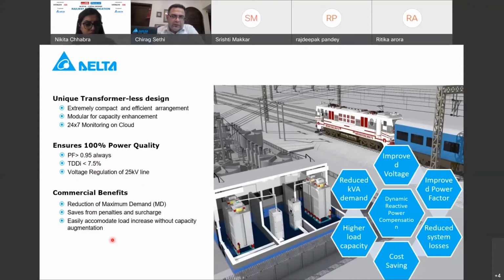Of course, the benefits to the customer include a reduction in maximum demand. Penalties are progressively coming at various state levels and in zonal railways, so there is a saving from the penalties and surcharges which are levied on consumers, that is, the railway user. It can easily accommodate load increase without capacity augmentation. Since we are improving the efficiency of the system and pumping in reactive power, in general, more load can be utilized on the same line.